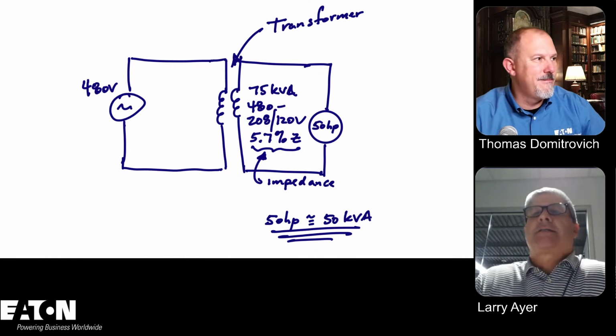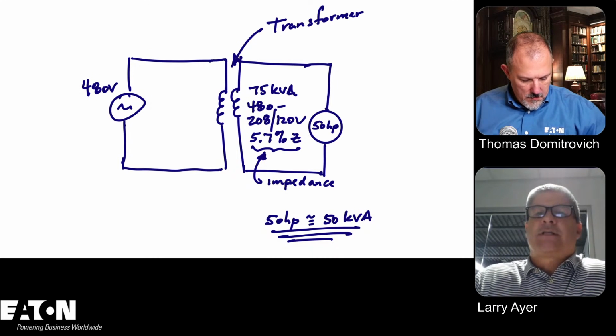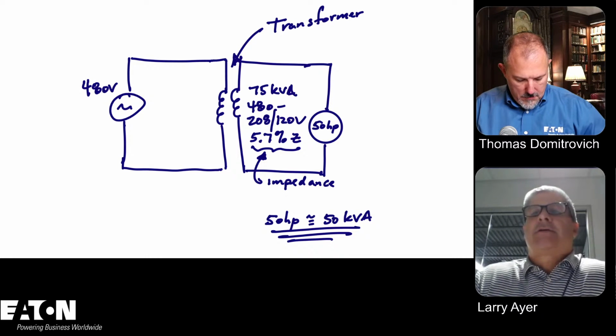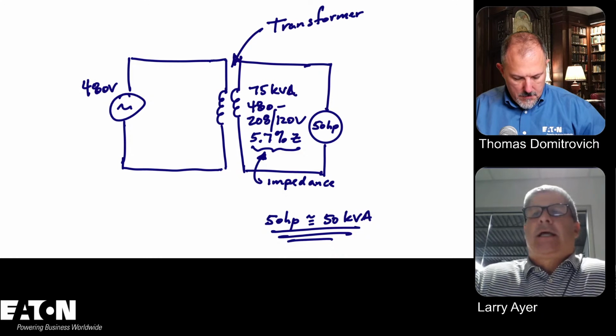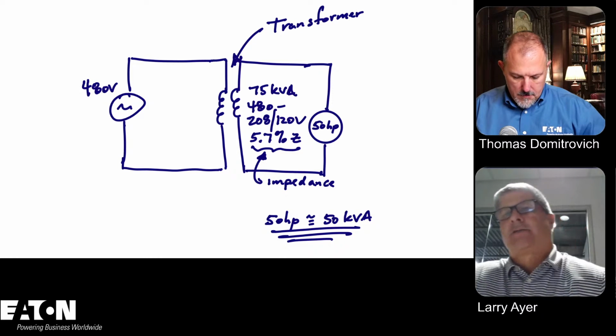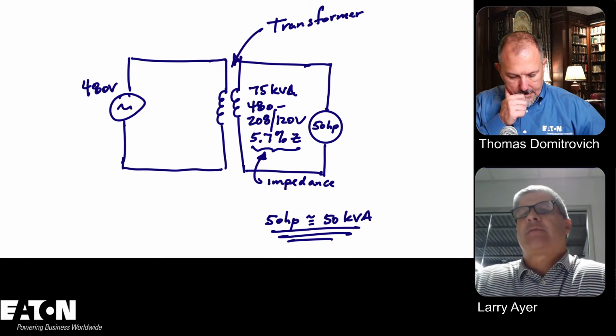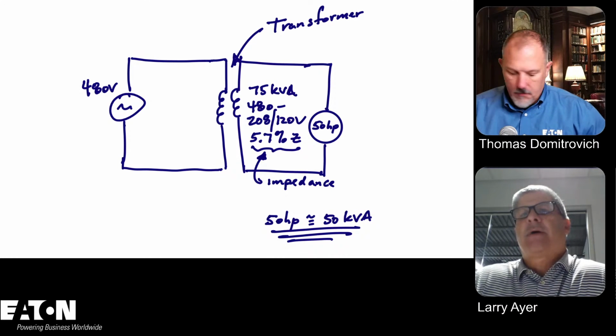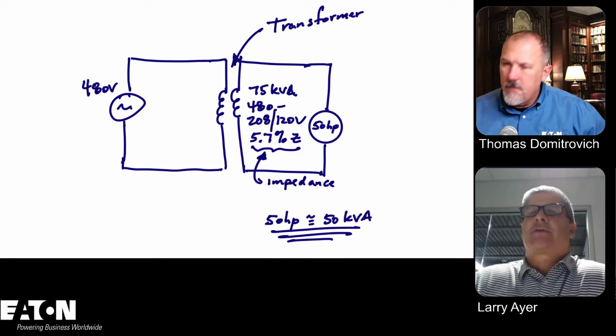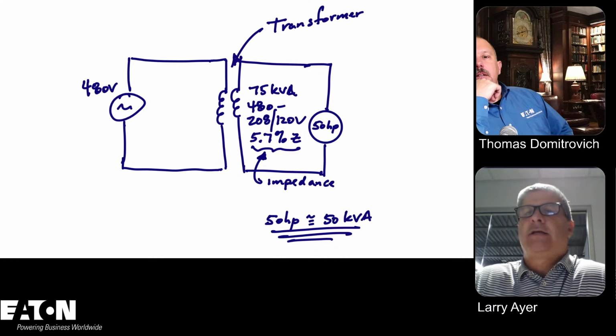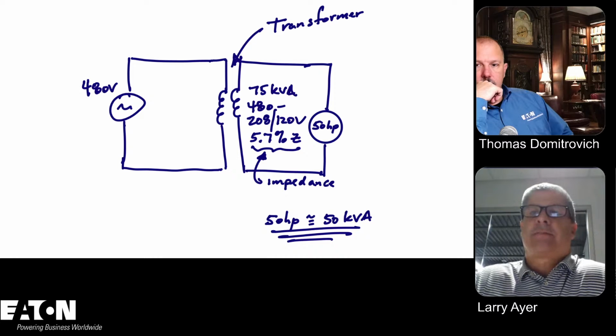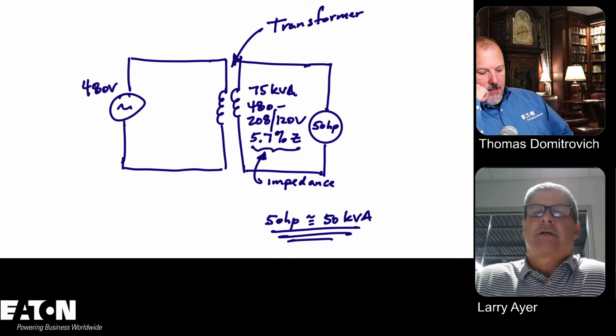If you go to the next one there, and this is kind of an example. So let's just take a standard transformer. A standard transformer has a 5.7% drop. Now, people always say, okay, I don't understand percent. What does that mean? And I've always struggled with that when I was younger. I think when you look at that 5.7%, it's really clear if you think about the whole system using percent. So if we were to consider 480 volt as the 100% rated voltage of the system, and we were to have 100% rated current, whatever we determine that full load current is. So if we have a 75 kVA transformer, 100% of the current flow on the primary is basically 90 amps. So if we had 100% voltage, 100% current, we would have a 5.7% drop. So I like to look at those things in those terms.